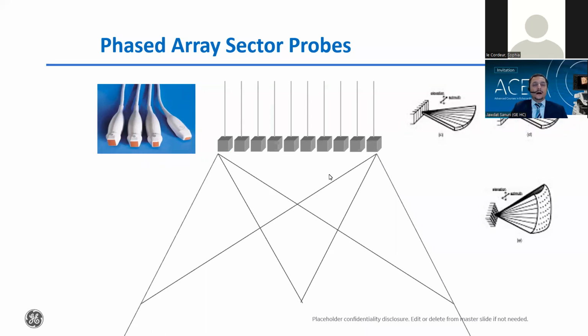Again, in the normal phased array probes, we have the line of elements that are providing us with a wide field of view. We also have matrix array 2D probes, which give us elevation focusing. However, we had to wait till the development of the matrix array with 40, 50, 60, 80 rows, as well as columns of elements, providing us with a pyramid-shaped volumic field of view up to 90 degrees by 90 degrees, a pyramid type of image originating from the tip, which is the surface of the probe.